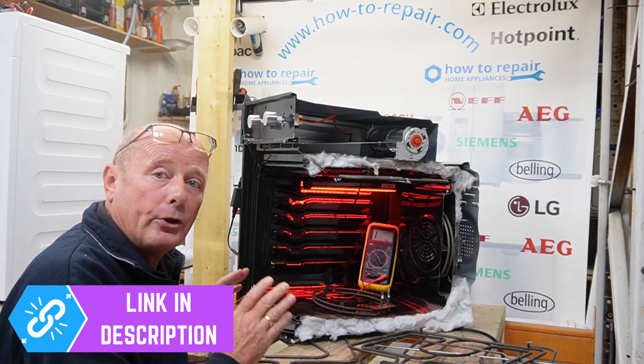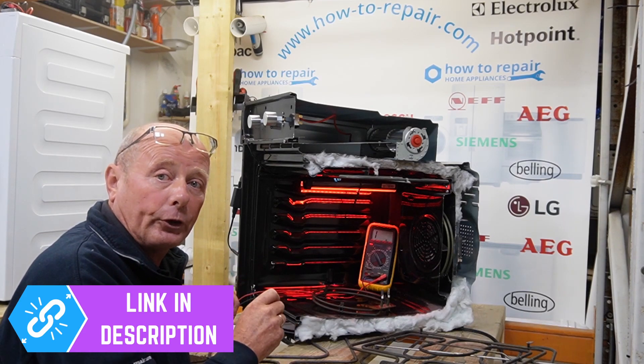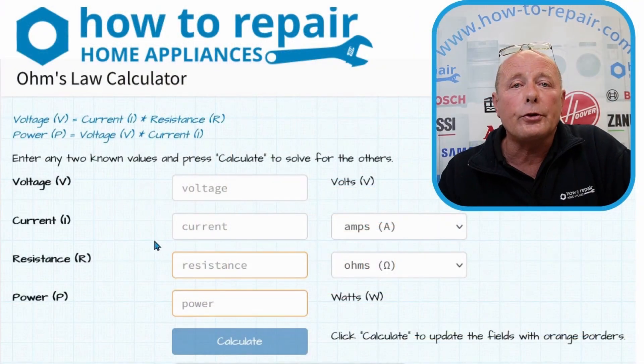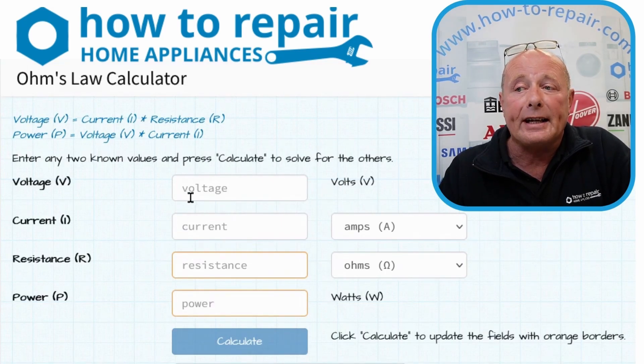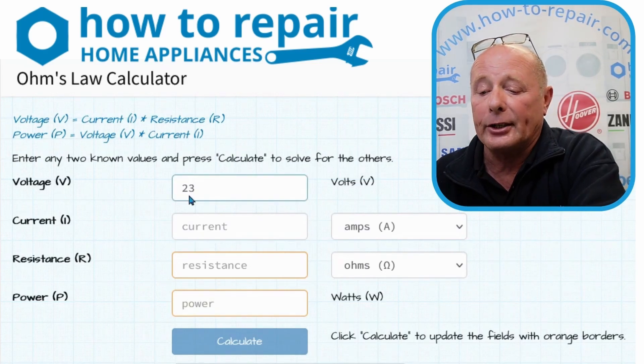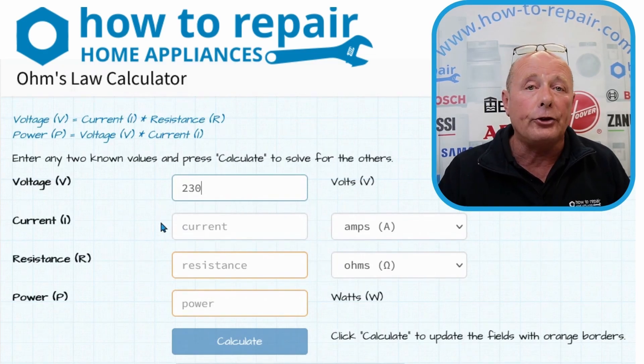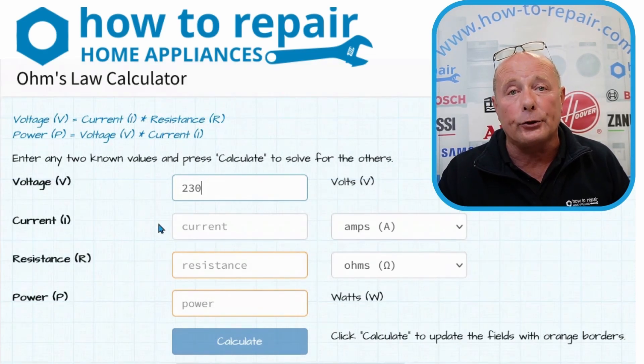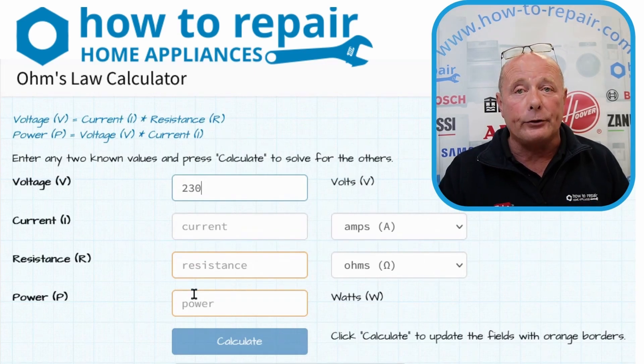We're just dealing with Ohm's law and I'm going to show you how to test elements using the calculator, which is also in the description below. For those of you who have never used an Ohm's law calculator before, let me quickly show you the three ways in which I use it. You always need a base voltage — we are testing at 230 volts, which is stamped on all the elements. Although we live in the United Kingdom and draw 240 volts, our voltage does vary between 230 and 240. You must also fill in one of the other three fields.